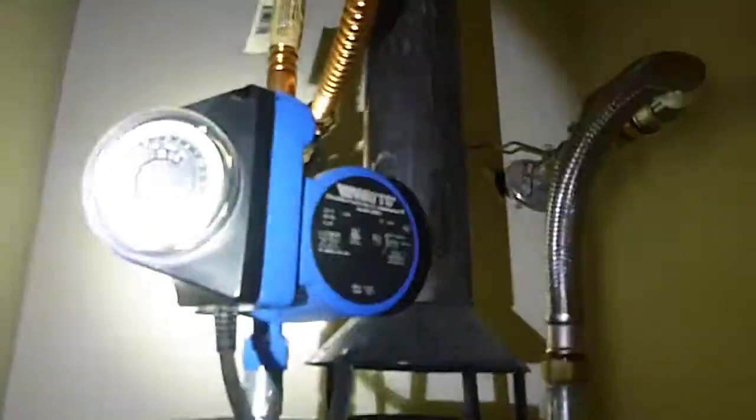That's the main grounding wire on the cold water side. We do have a circulating pump. These lines are not insulated. The TPR is not insulated. It does have a vacuum breaker. It does have a care and use manual. This guy is also 40 gallons, 2008. They last about 10 years, by the way.